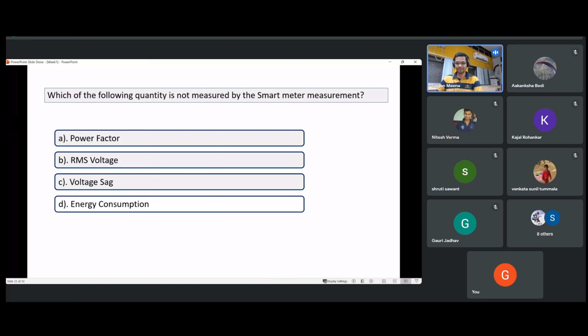Current, correct, Sunil. Any other? Reactive power, correct. We can measure active power, energy consumption, reactive power, RMS voltage, RMS current, and power factor. But voltage sag is not measured by smart meter, because it is not instantaneous — it is not decided based on instantaneous RMS voltage. Let us see the definition of voltage sag in the next slide.